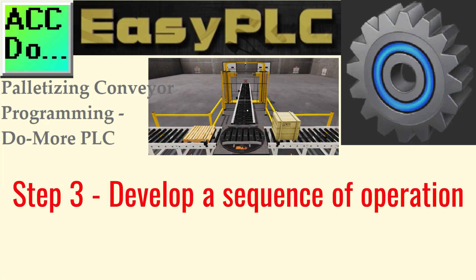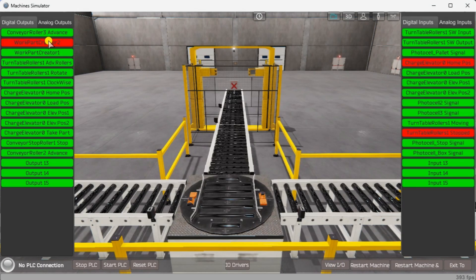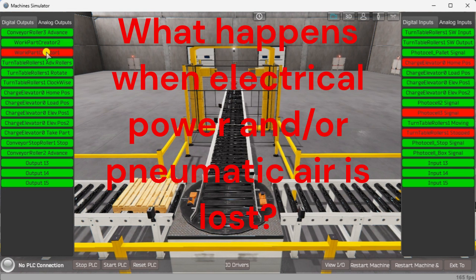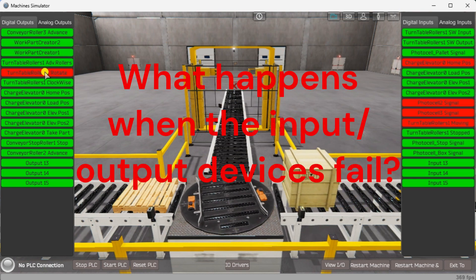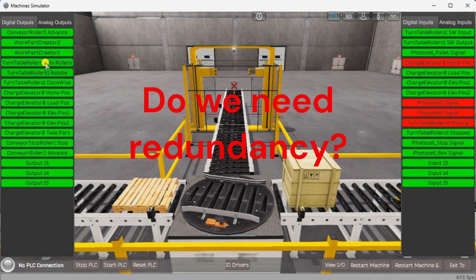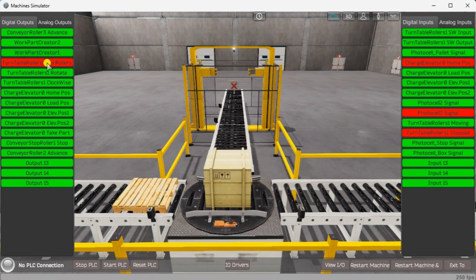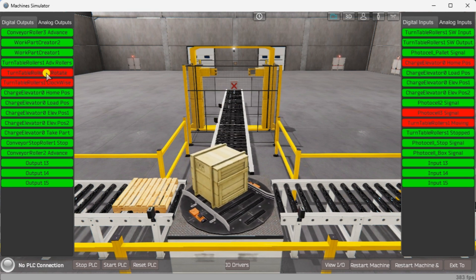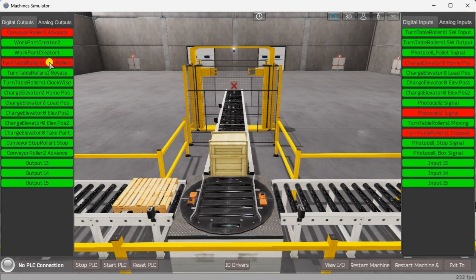Step 3: Develop a logical sequence of operation. A flow chart or sequence table is used to thoroughly understand the process that must be controlled. It must also answer questions like: What happens when electrical power or pneumatic air is lost? What happens when inputs and output devices fail? Do we need redundancy? This step is where you'll spend most of your time. Understanding everything about the operation will save you time and help prevent you from continuously rewriting your PLC program logic. Knowing all these answers up front is vital in developing the PLC program.